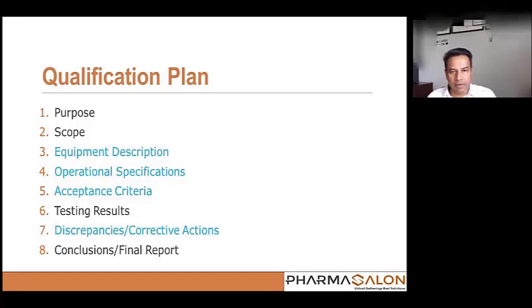For example, autoclaves, dry heat ovens, pH meters, any of the manufacturing equipment: when you purchase them, there is a clearly defined purpose, and you define the scope of use, and this can be qualified by calibration and validation. Calibration is a process of making sure that particular equipment meets the parameters stated by the manufacturer. And validation is a process where we verify that the equipment is able to perform the desired function at the facility. So these things need to be defined prior to qualifying an equipment at a manufacturing facility.